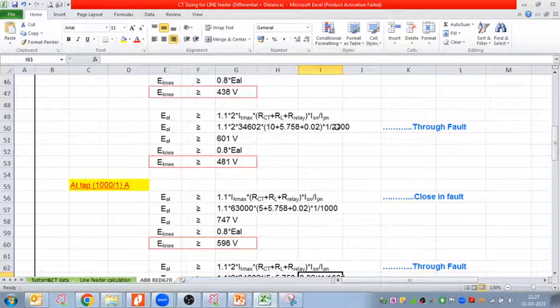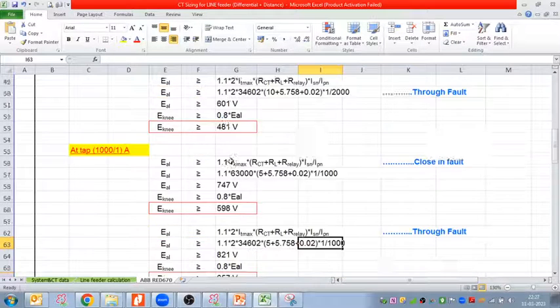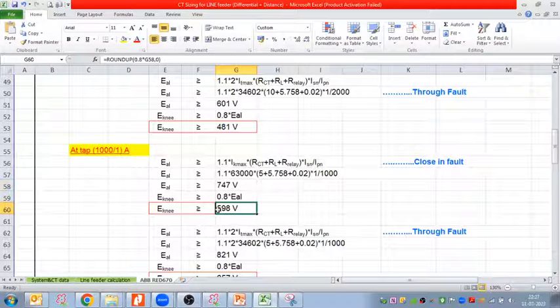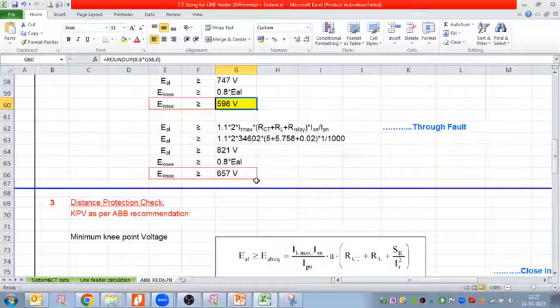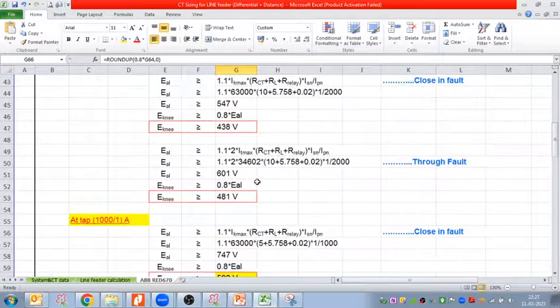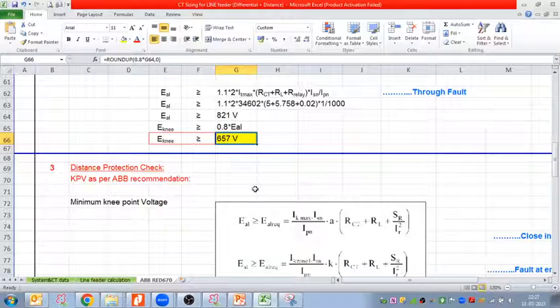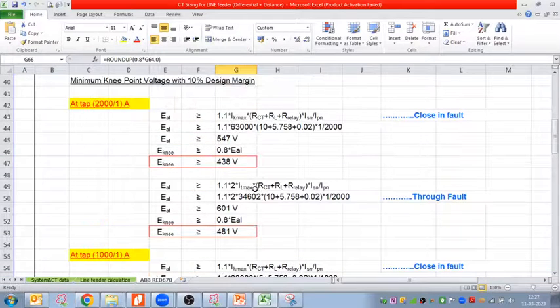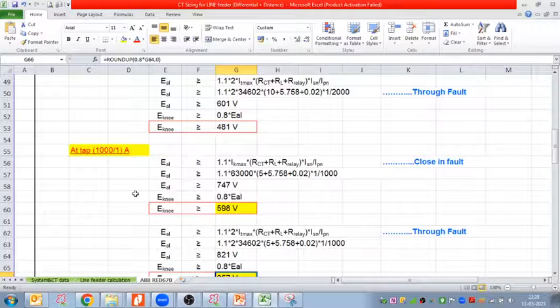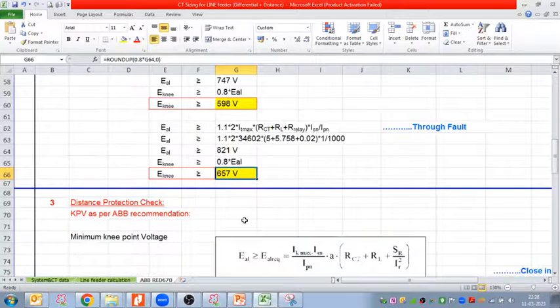So this is initially 2000, now it is 1000. So what will happen? This much is going to increase. This much is 747 volts or 598 volts, and for the through fault case 657 volts. So now out of 4 you take, and for the 2000 tapping the maximum of these 2, and for the 1000 tapping the maximum of these 2, we can select the CT knee point voltage.